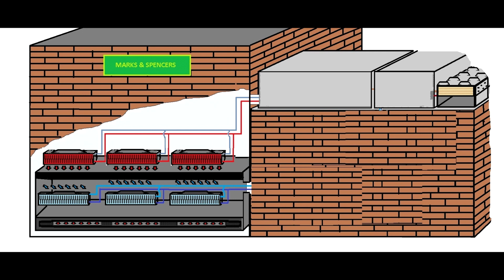So I had a look into it, and after I figured out how the system works, I went on the roof. What you'll see surrounded by the yellow circle is the heat recovery system, and on the right hand side there's the condenser. Sometimes you don't want to recover the heat because the store is too hot, and then you dump the heat out through that condenser.